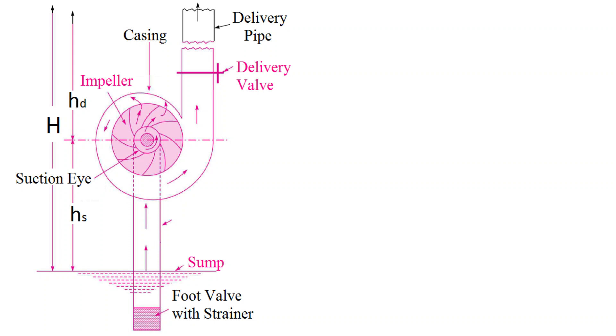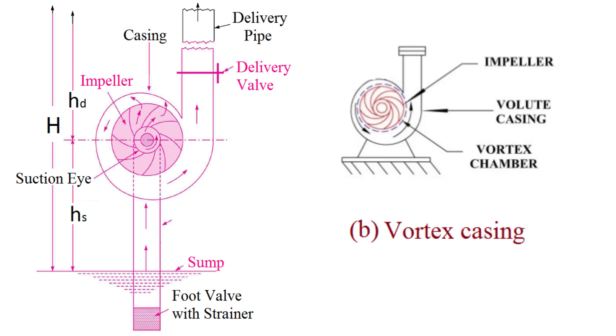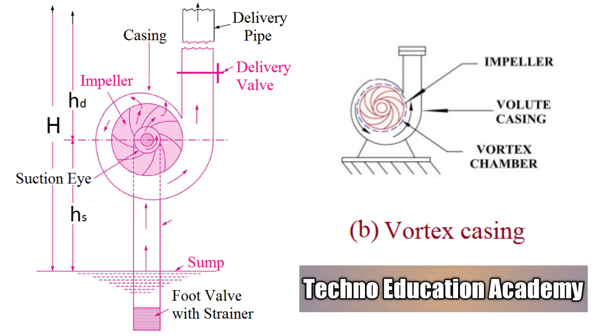Second one type of casing is vortex casing or whirlpool chamber type. This is an improved type of volute chamber. Here an annular space is provided between the volute and impeller forming a combination of spiral and circular chamber. The arrangement reduces eddies to a considerable amount and improves the performance of the pump.